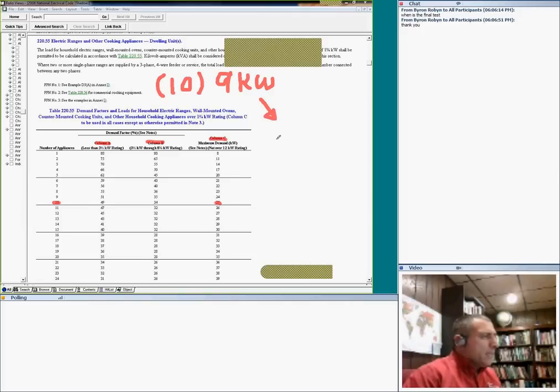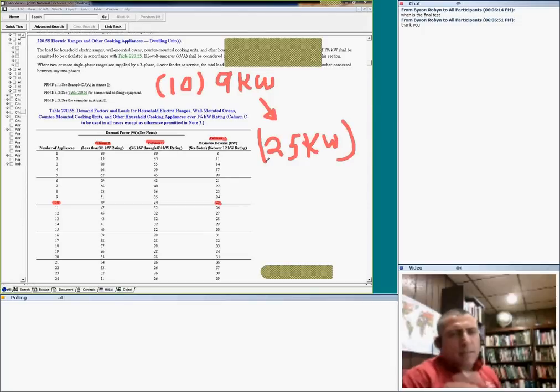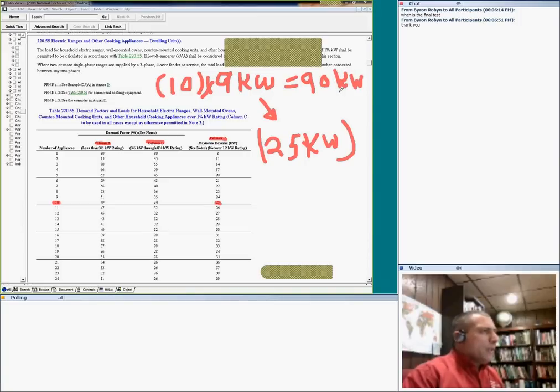So these 10, when I demand them, they're demanded as 25 kW. And the most confusing thing, guys, is what is the demand? If you multiply 10 by 9, that gets you 90 kW. Can you see, Gerald, my friend? Can you see we went from 90 kW all the way down to 25 in residential.